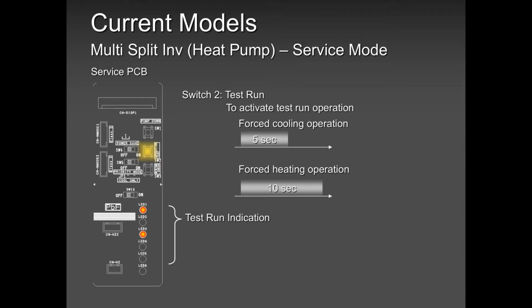So some guys like using test run after they finish their job. I don't mind you guys using test run, but my problem is if you crossed wires, okay? And I have seen guys with 40 years experience, 30 years experience, 20 years experience, they cross wires by mistake. I don't blame them. So that can be a problem in test run, because when you cross wires, all indoor units are running. So you will not see that problem. That is my only drawback.